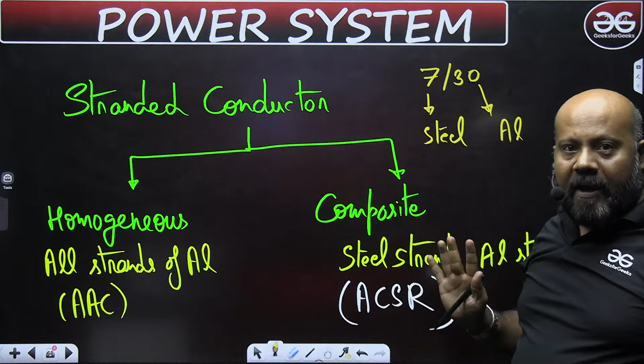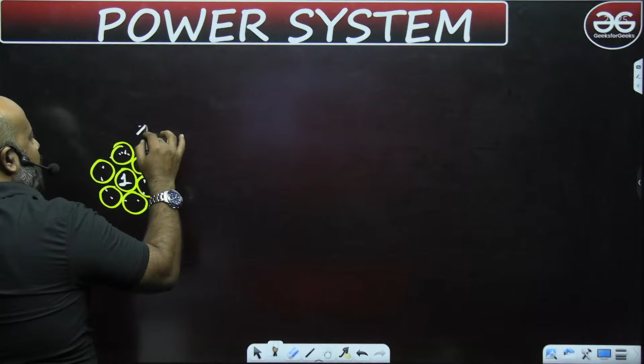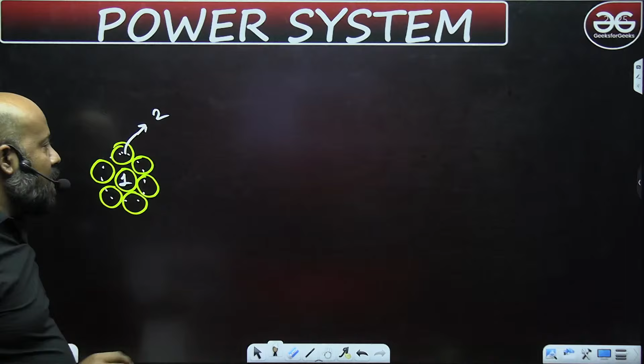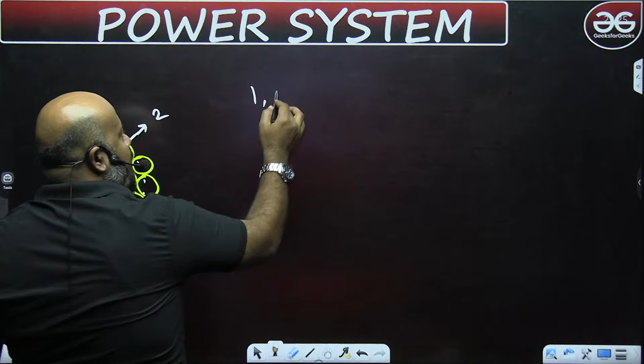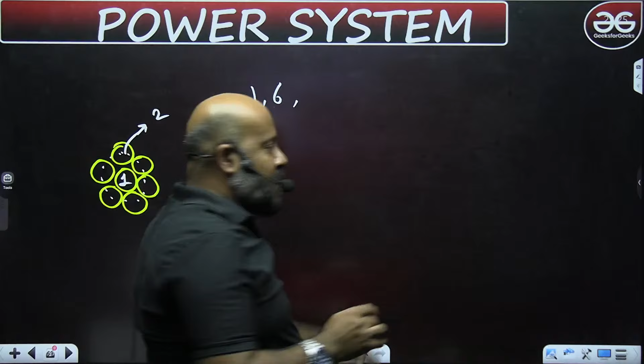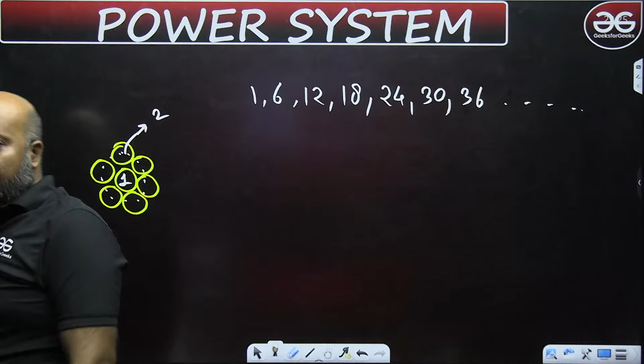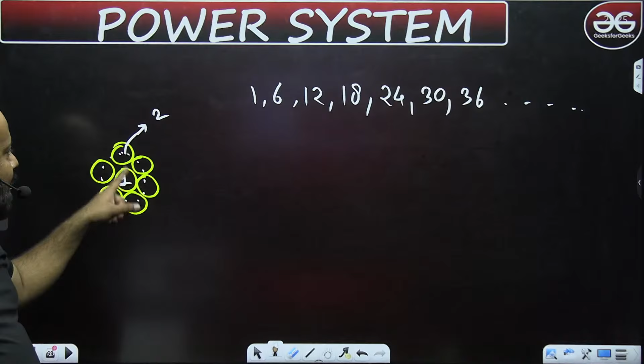Now, if you talk about the stranded conductor, listen, this is very important. This is the core strand, which we call layer number 1. This is what we call the second layer, and in the second layer you have 6 strands. So the pattern is: first you have the core strand, then the next layer has 6, then strands in multiples of 6: 6, 12, 18, 24, 30, 36, and so on. At the core you have 1, and the next layer, the second layer, you have 6.